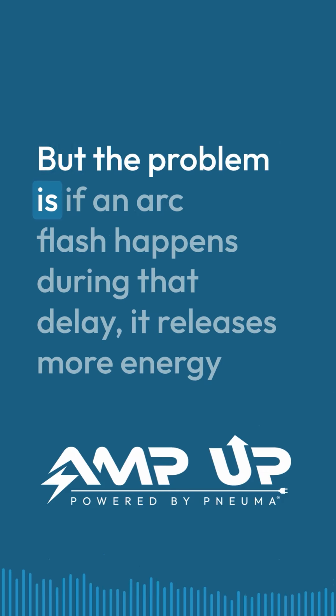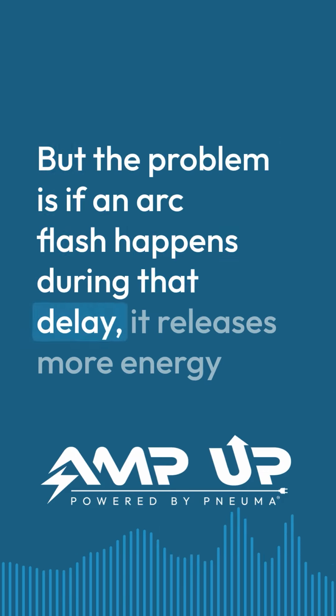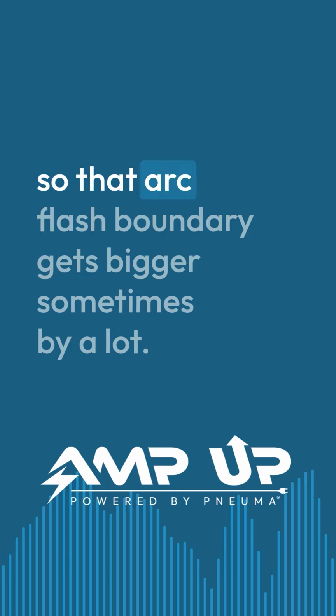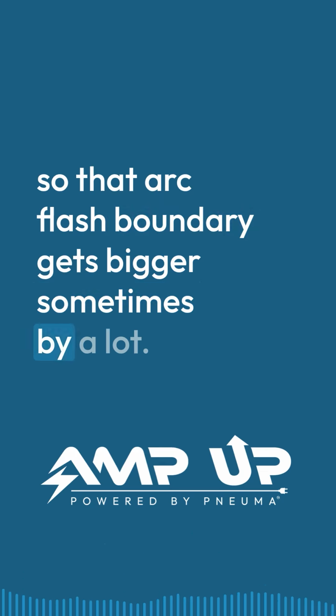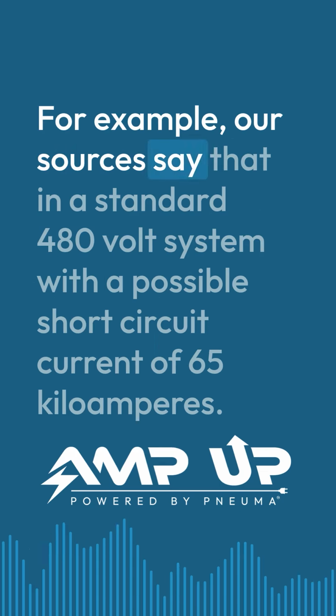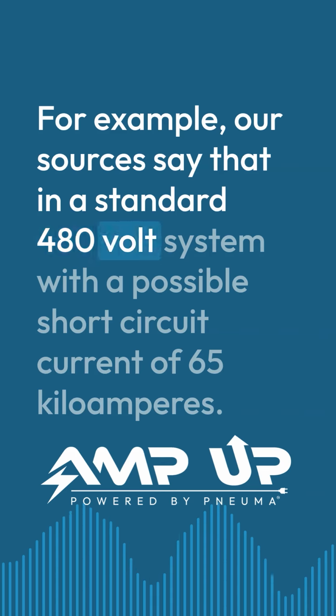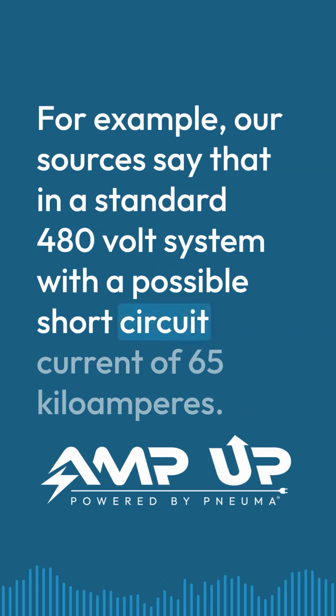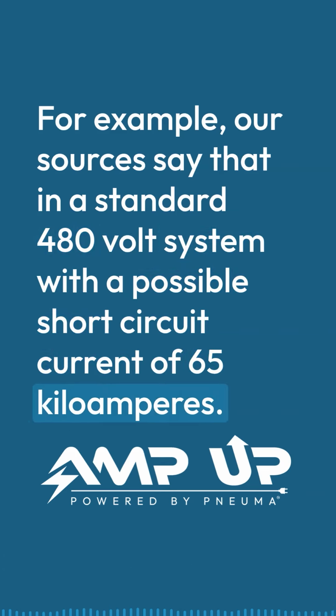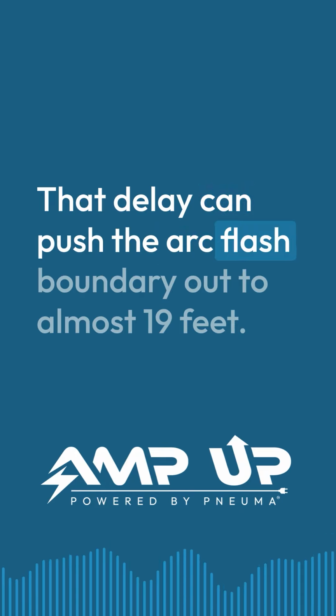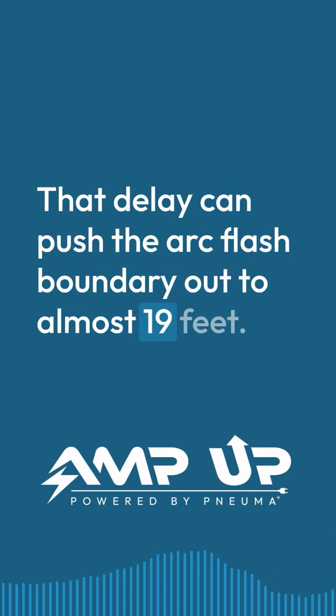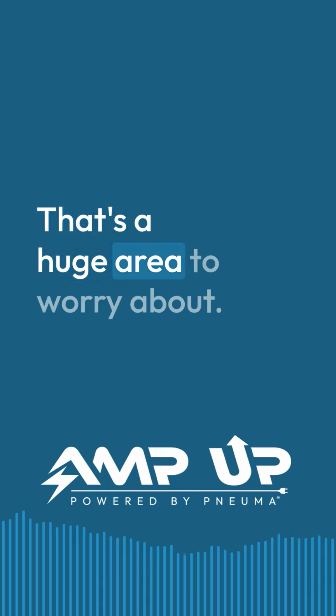But the problem is, if an arc flash happens during that delay, it releases more energy. So that arc flash boundary gets bigger, sometimes by a lot. For example, our sources say that in a standard 480-volt system with a possible short circuit current of 65 kiloamperes, that delay can push the arc flash boundary out to almost 19 feet. 19 feet, that's a huge area to worry about.